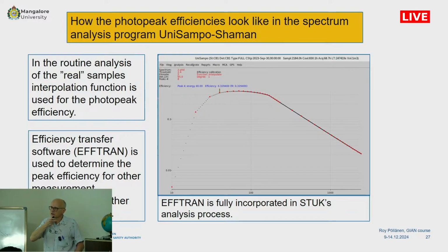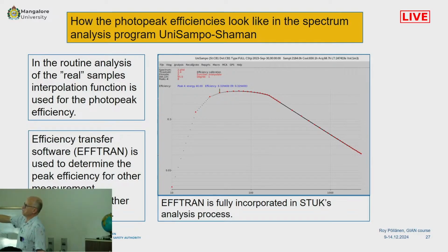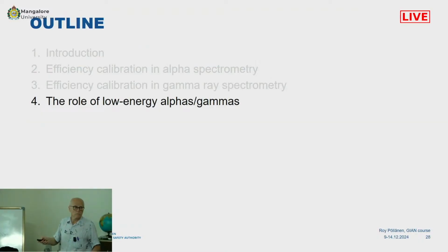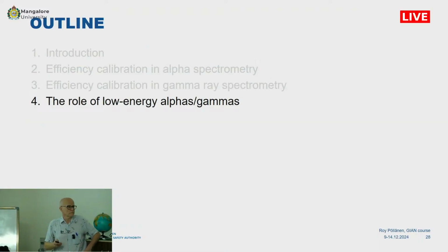Are you using functions in your efficiency calibration? I mean that if some nuclide is in this area, around, let me say 40 kiloelectronvolts, are you using a function or a linear interpolation? We use linear. Linear, yeah. All right. But the software has the option for both. Yeah. It has an option called dual energy. Yeah. For the higher energy one side.